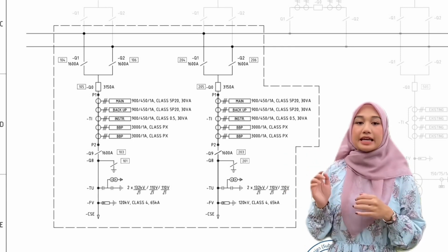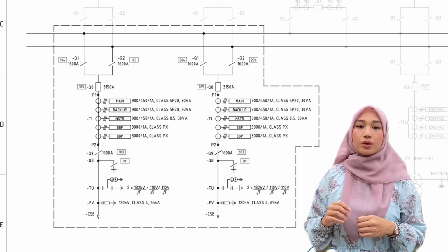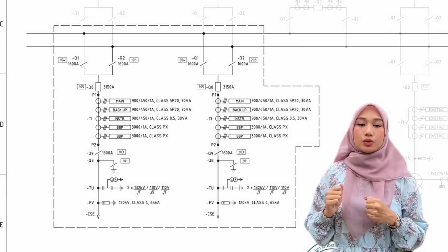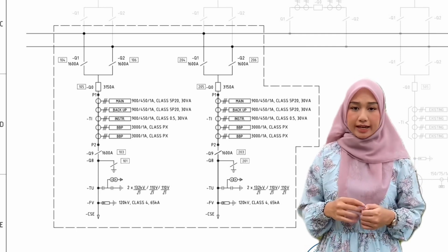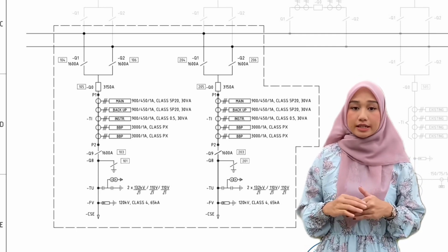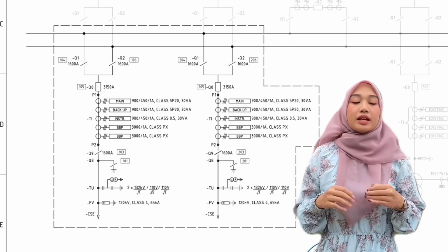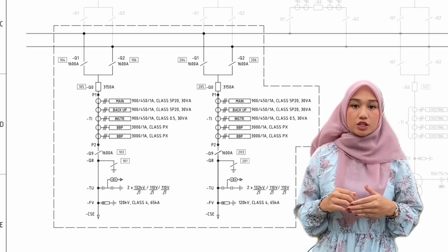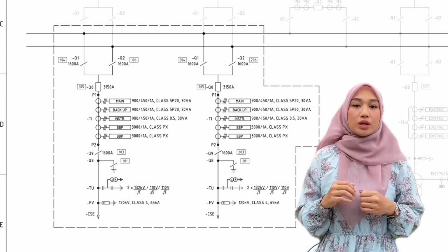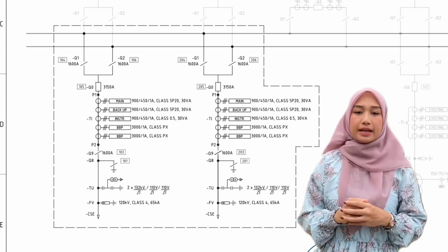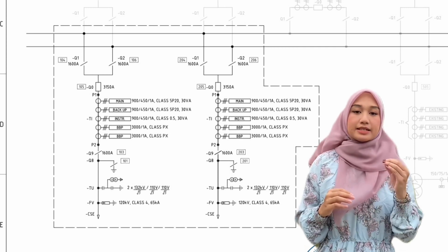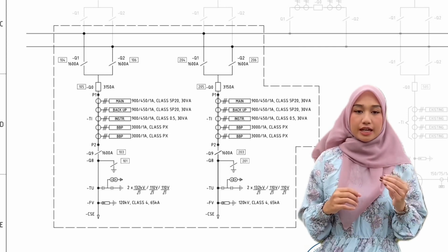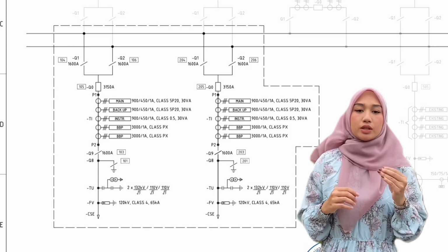And from the bus bar, it is connected to Q0, which is the circuit breaker, to the T1. T1 is the current transformer which is connected to Q9 line disconnector, or in a small circuit acts like a switch. It is then connected to earthing switch Q8, then to the TU, which is the capacitive voltage transformer, and then to the surge arrestor FV, and lastly to the CSE, cable sealing end. CSE is the interconnection between the switchyard and the underground cable.